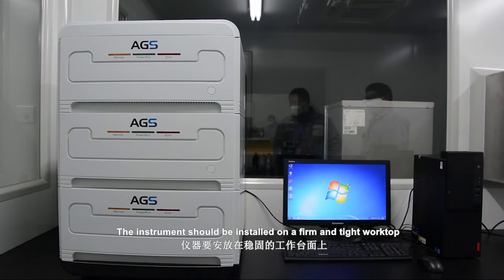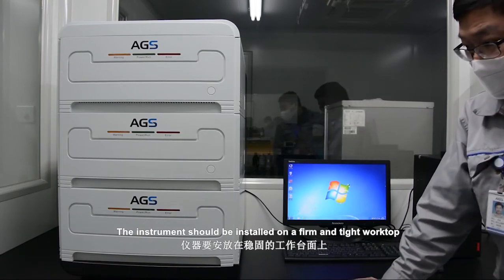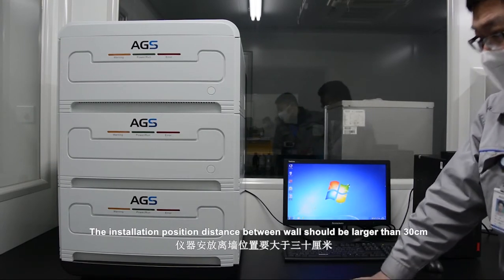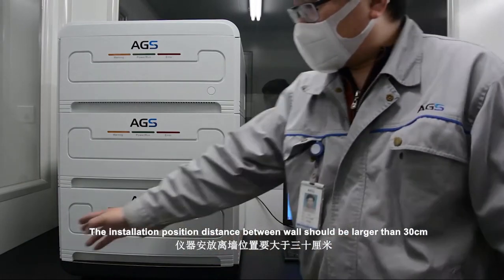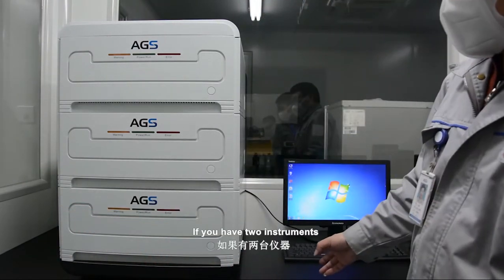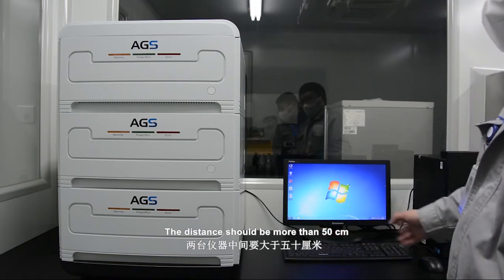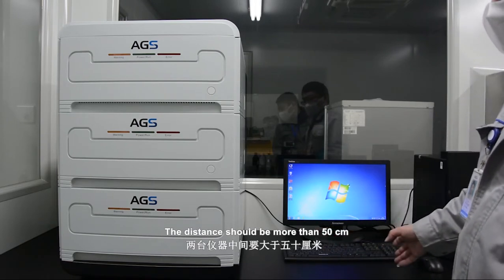The instrument should be installed on a firm and tight worktop. The installation position distance between wall should be larger than 30 cm. If you have two instruments, the distance should be more than 50 cm.